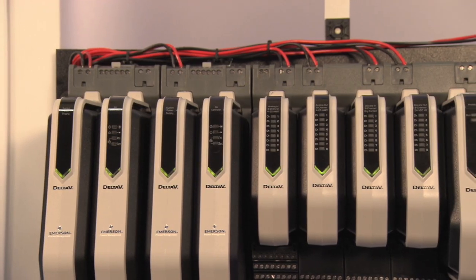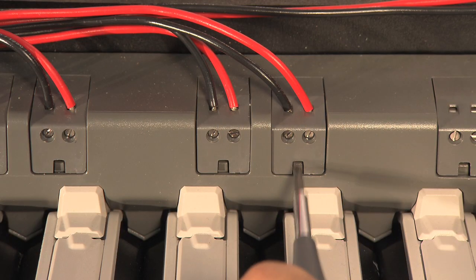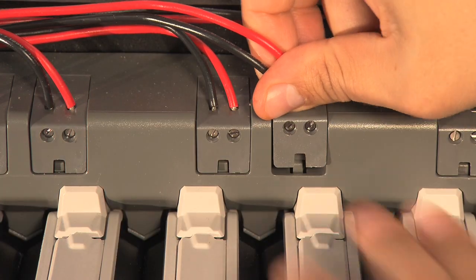We have also improved the wiring of the field power by reducing work and reducing complexity. Now you can have 24-volt redundant bus power in the backplane, or you can have individual power injected to your cards.